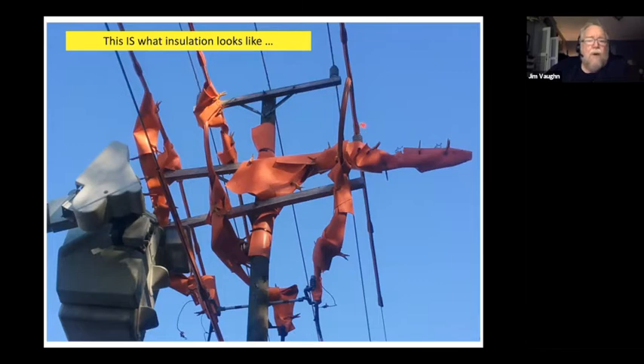But any place that we're going to move a phase, if that phase can come in contact with a grounded surface, then MAD matters. Once I untie this phase and I pick it up, MAD, minimum approach distance, doesn't just apply to the worker. It also applies to the grounded surfaces within that work area. And here's why. Under normal conditions, when this conductor is tied down, then the only thing we worry about is the air gap to prevent flashover.